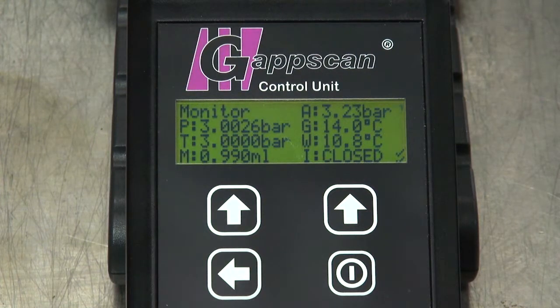G and W are the inlet and outlet temperatures, which are not that important. We do keep a record of these though, as if, for example, someone accidentally put steam into the system, we'd get really high temperatures and a false reading, but we'd be able to see why. I indicates whether the valve within the Gappscan unit is open or closed.